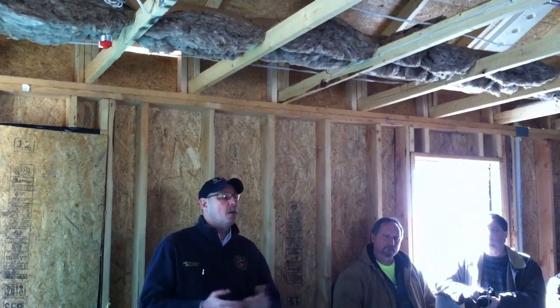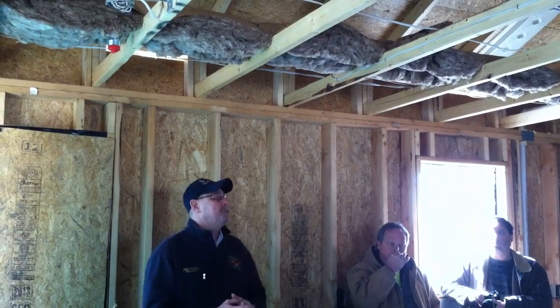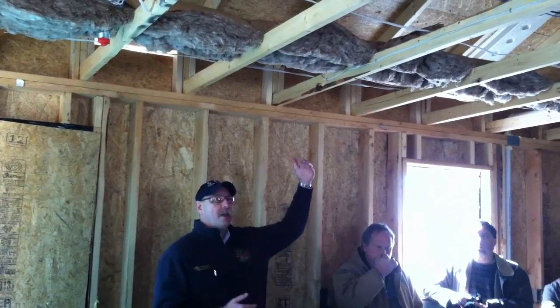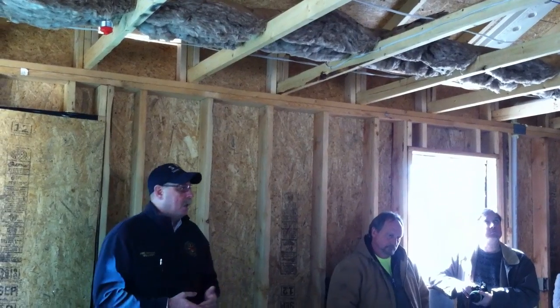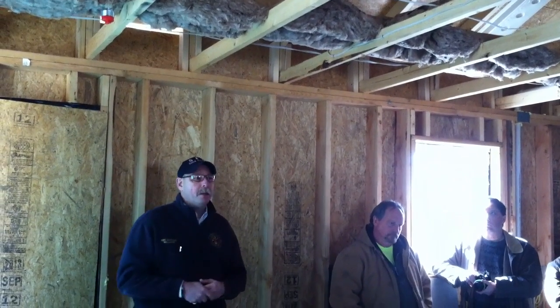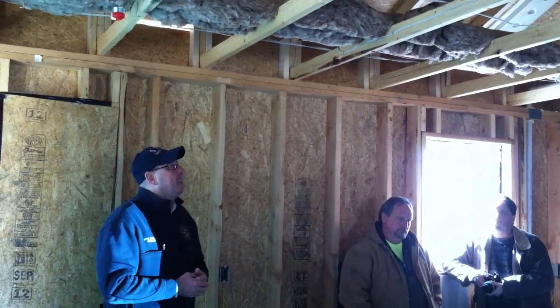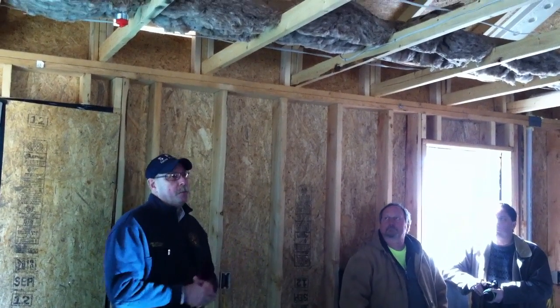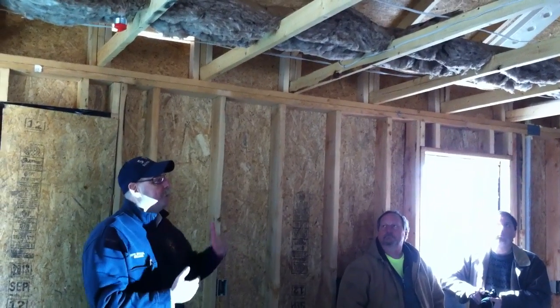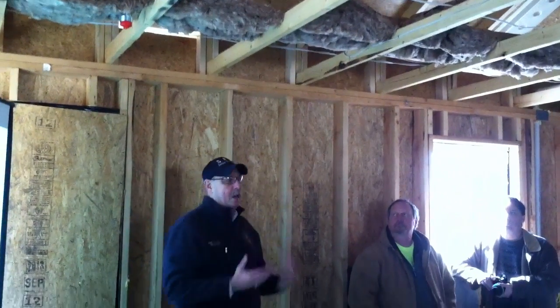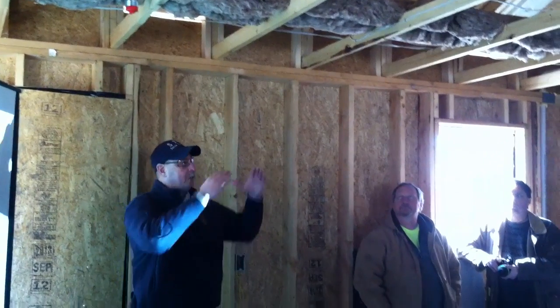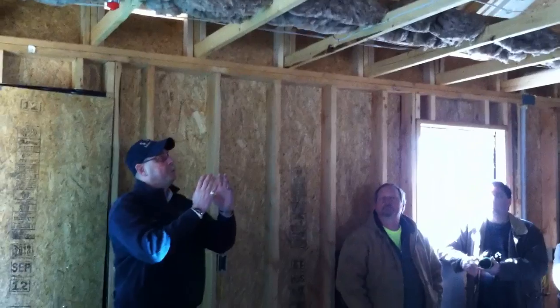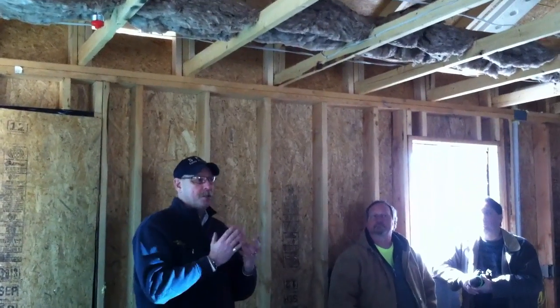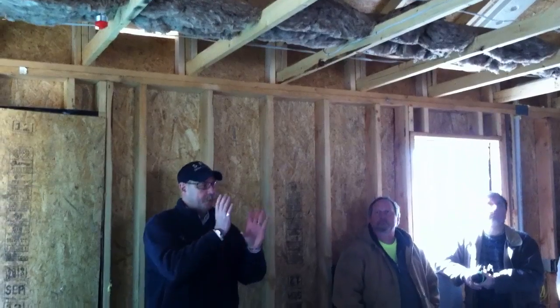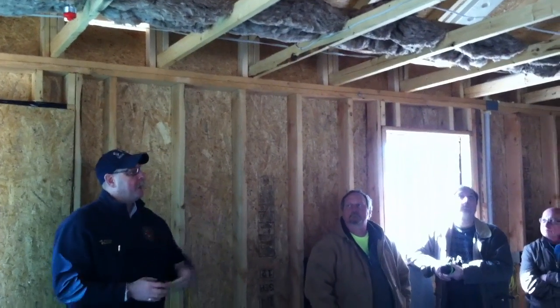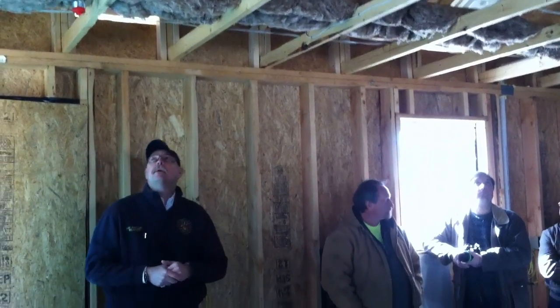One of the other code requirements, since we're in Kansas and subject to freezing, is that any pipe in the attic has to be tented. There was a question earlier about wrapping the pipe—you can do that, but as we discussed, the issue is that the design of tenting is to allow radiant heat to get up into that cavity and keep the pipe warm, whereas if it was completely wrapped, you wouldn't be able to get that heat onto the pipe itself.